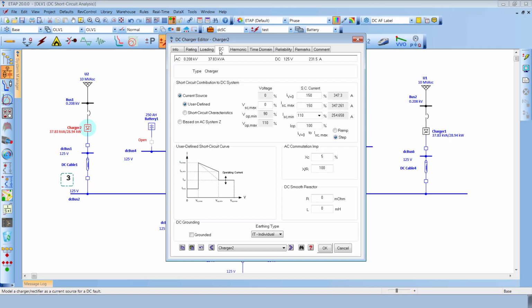The short circuit page, however, explains the contribution of the short circuit current to the system depending upon its terminal voltage and the corresponding voltage percentage depending upon the location of the fault. To demonstrate the actual contribution of the charger, it is important to fault a bus at a time and examine the terminal voltage of DC bus 1 to which the charger 2 is connected.